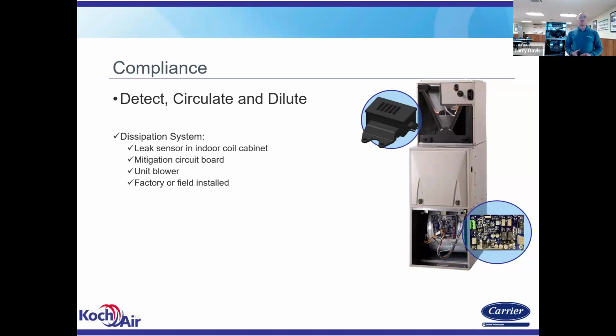This is, again, just a reminder, the dissipation is what we're using to be compliant with UL on this. So we detect a leak, we disable our heating or cooling system, and engage our fan to dissipate that refrigerant out into the space so that the percentage of refrigerant to the air is below the lower flammability limit. You're going to be in dissipation at least 15 minutes before anything will come on and run again.